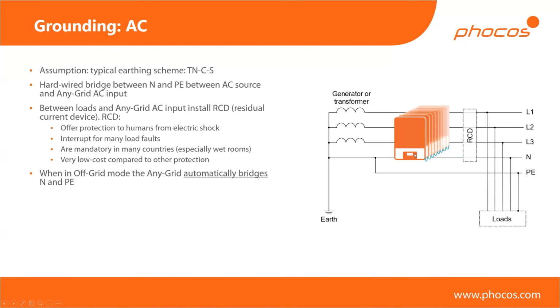So what the AnyGrid actually does internally, that's the last point here, is automatically bridge the neutral and ground wires. That will simply ensure that if you're disconnected from the grid, this bridge, which is absolutely important for the residual current device to work at all, is made inside the device on the fly, to make sure that your residual current device will always protect people from electric shock if ever they touch any of the phases or the neutral conductor.